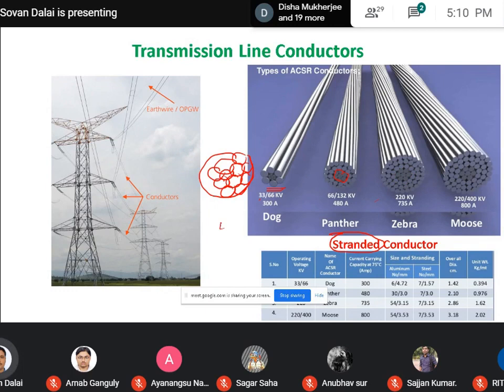Generally, this type of conductor is known as ACSR conductor, aluminium conductor steel reinforced. Aluminium conductors are used for lighter weight, and the steel conductor is used to provide the mechanical strength. According to the voltage level, if I want to use a standard conductor for the 33 kV to 66 kV range, generally we consider this type of configuration.